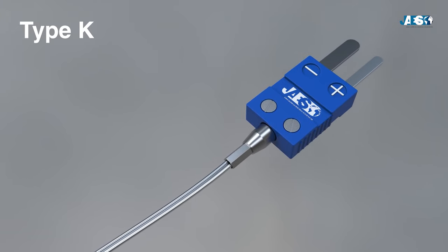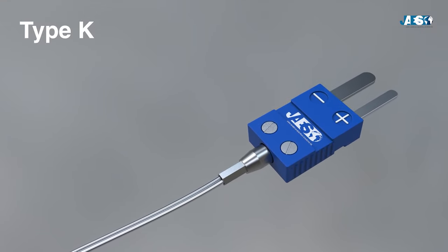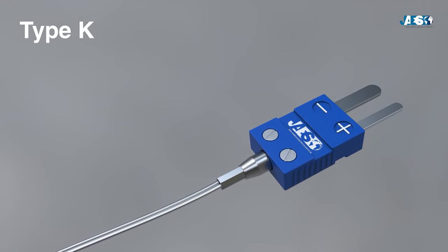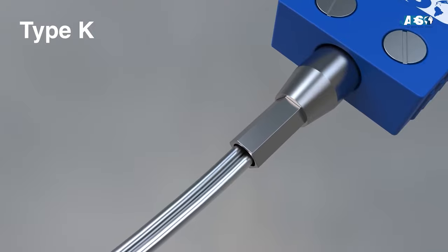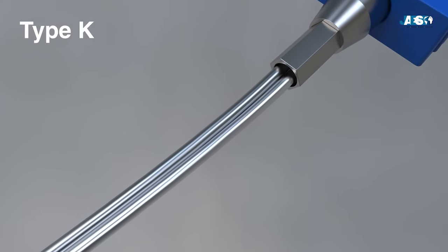The model marked with the letter K is the most common, cheap, and available in many formats. Composed of Chromel and Alumel, it detects a measurement range from negative 200 degrees Celsius to 1,260 degrees Celsius.